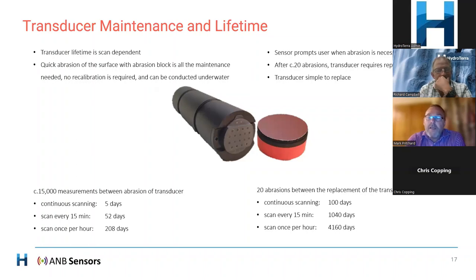If you're in a continuous scanning mode, and today our continuous mode is one reading every 23 seconds, you need to refresh the face of the transducer every 5 days. That's really a scrub of the face with a wet and dry sandpaper block. It's as simple as that. You can do that in situ, underwater, or take it out, scrub it and put it back in the water, and it will continue sensing.